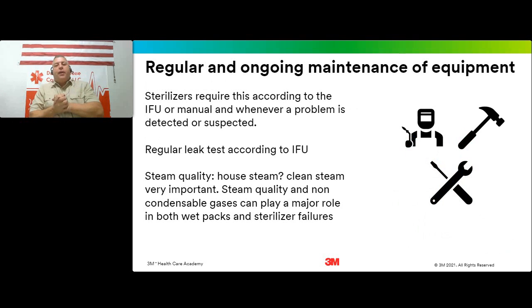Regular and ongoing maintenance of equipment. The sterilizers themselves - it is crucial that the sterilizers, they're medical devices. The sterilizer has its own IFU, and you shouldn't see service personnel in there just when something fails or the machine breaks, so to speak.